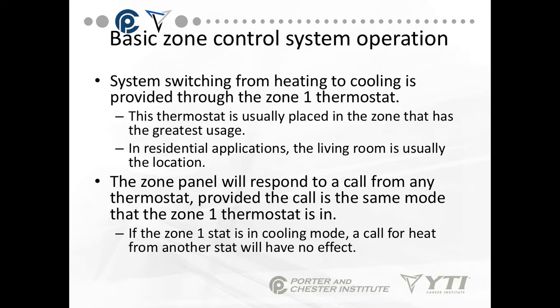The system switching from heating to cooling is provided through the Zone 1 thermostat, which is usually placed in the zone with the greatest usage — in residential applications, the living room is usually the location. The zone panel will respond to a call from any thermostat provided the call is in the same mode — heating or cooling — that the Zone 1 thermostat is in. If Zone 1 is in cooling mode, a call for heat from any other thermostat will have no effect.